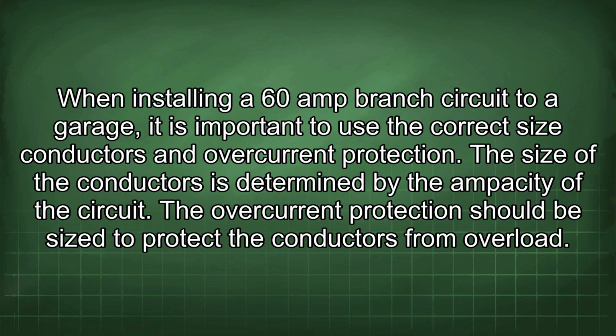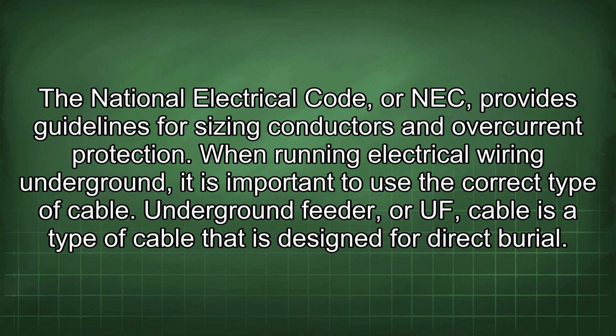When installing a 60 amp branch circuit to a garage, it is important to use the correct size conductors and overcurrent protection. The size of the conductors is determined by the ampacity of the circuit. The overcurrent protection should be sized to protect the conductors from overload. The National Electrical Code, or NEC, provides guidelines for sizing conductors and overcurrent protection.